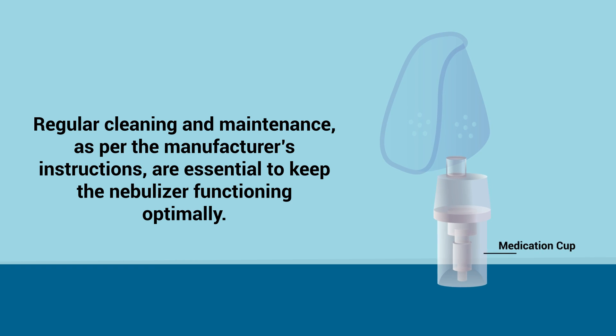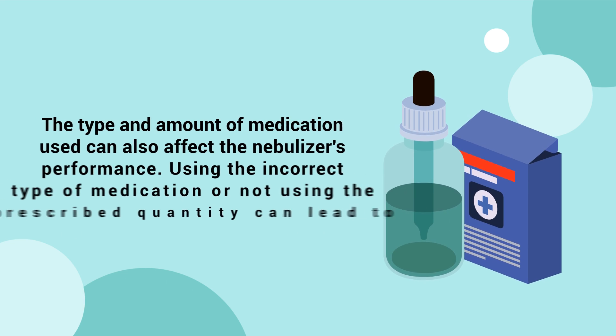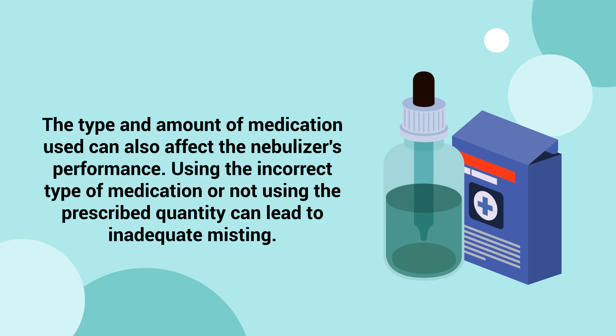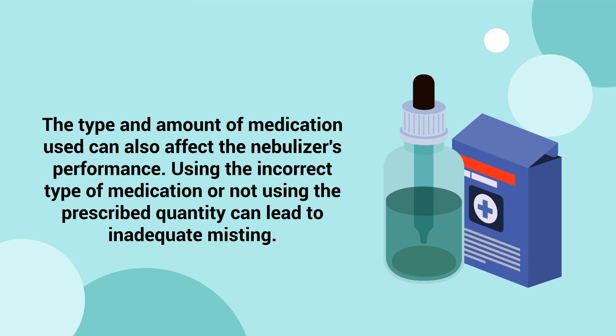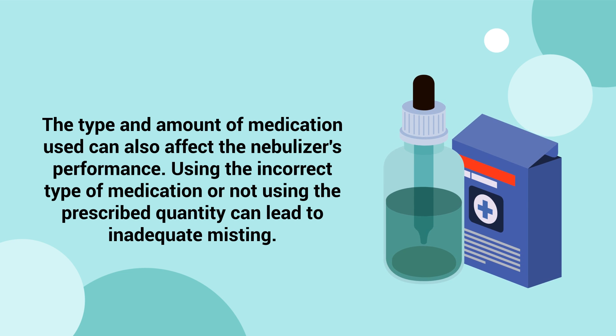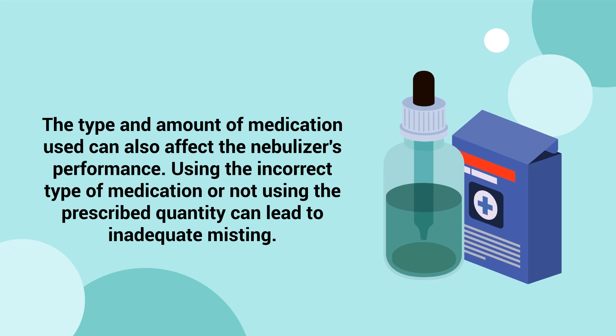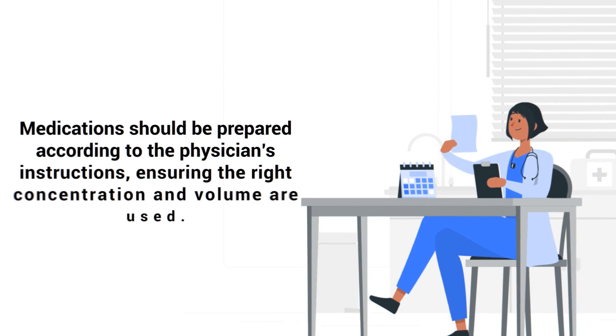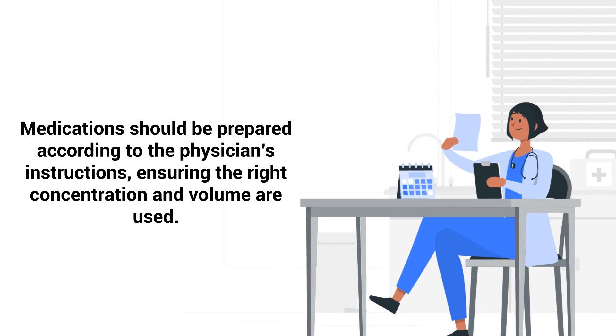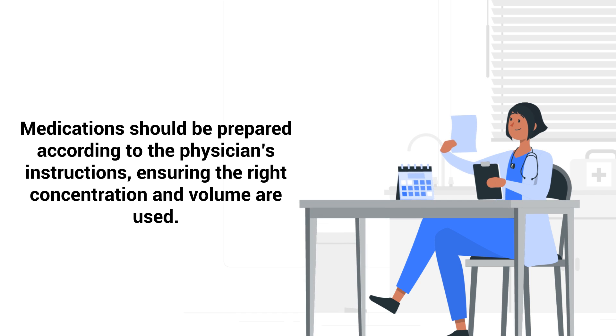Regular cleaning and maintenance as per the manufacturer's instructions are essential to keep the nebulizer functioning optimally. The type and amount of medication used can also affect the nebulizer's performance. Using the incorrect type of medication or not using the prescribed quantity can lead to inadequate misting. Medications should be prepared according to the physician's instructions, ensuring the right concentration and volume are used.